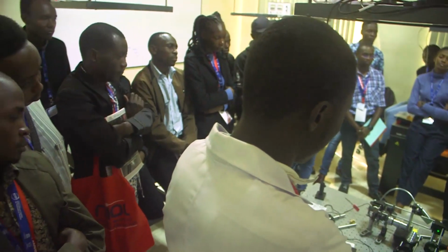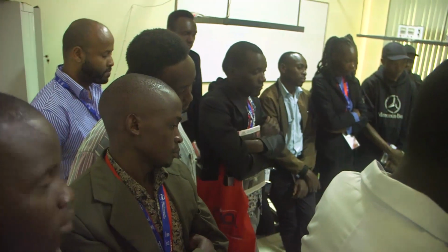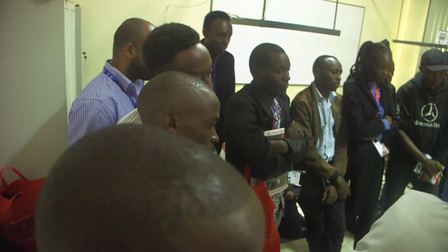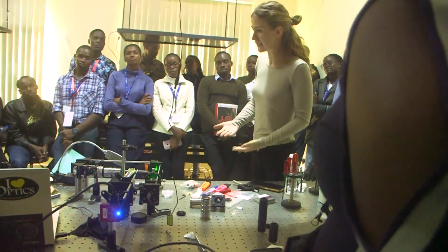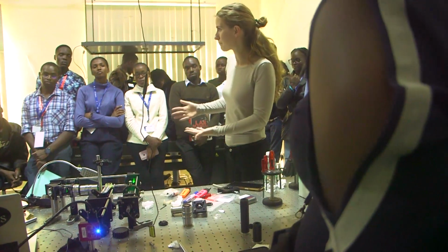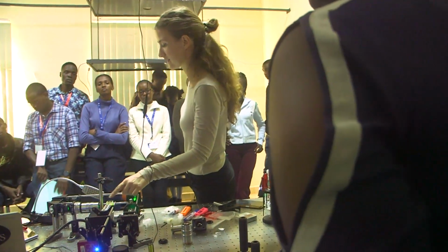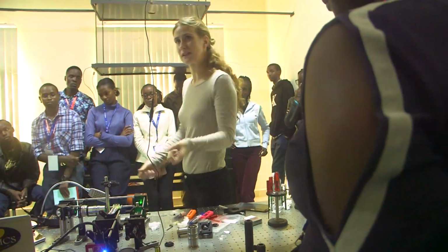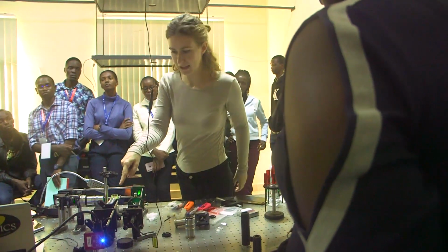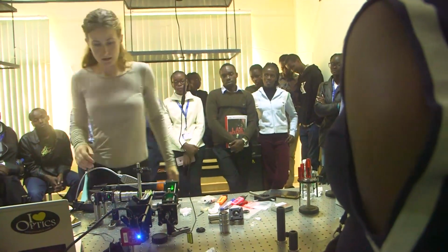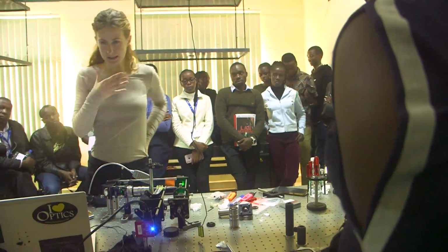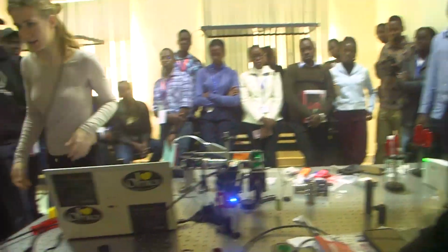But if I start with a cuvette full of water and then I put my bag of water inside and I move it, the overall index of refraction, the overall optical path that the light will experience will always be the same, because I'm matching the index of refraction of everything that is inside here. So I put this because I know a priori that I'm going to put something in there that is full of water.